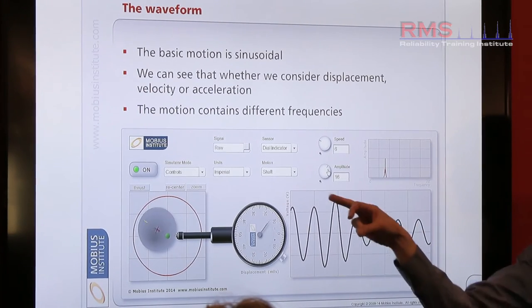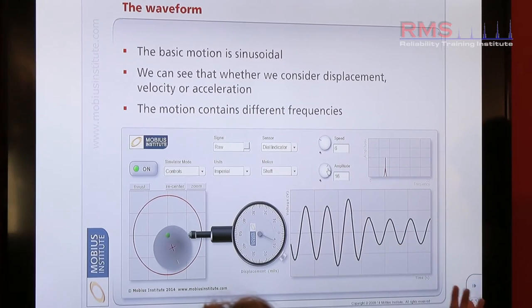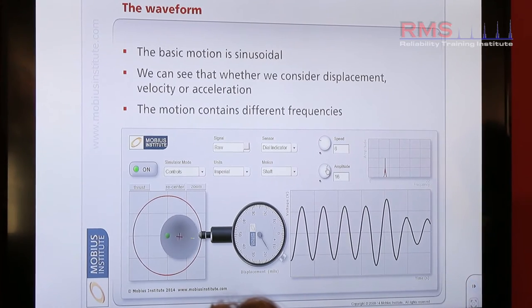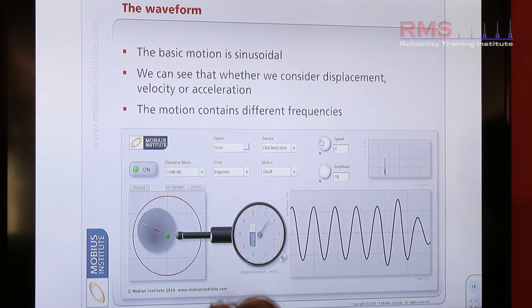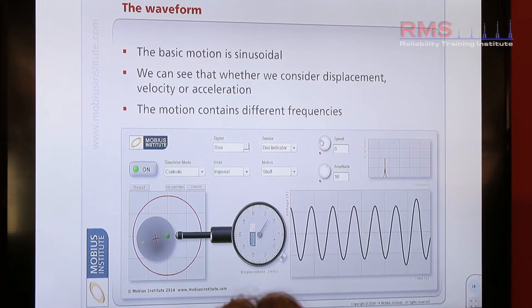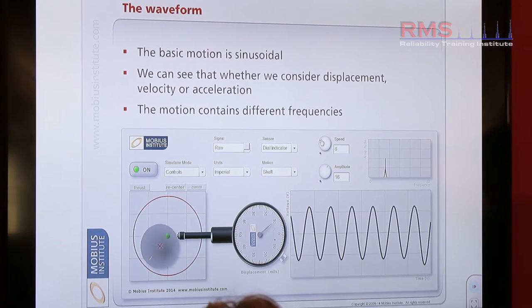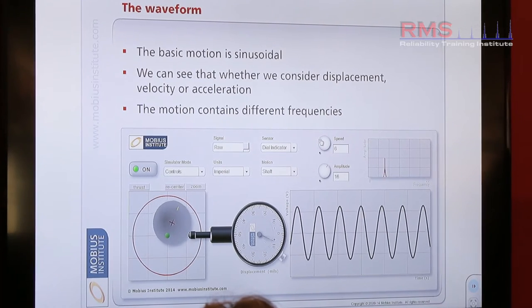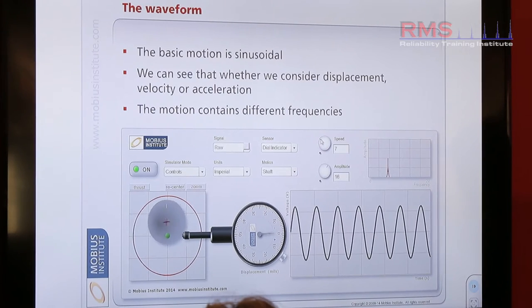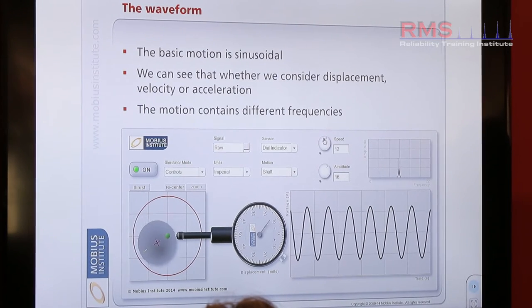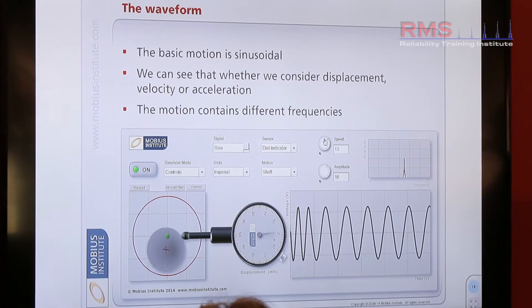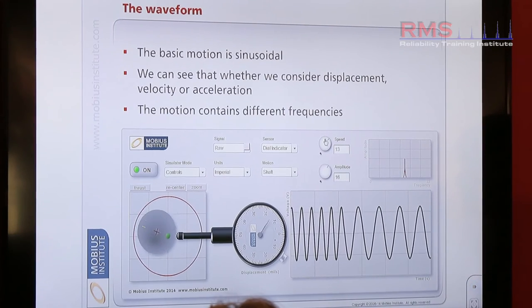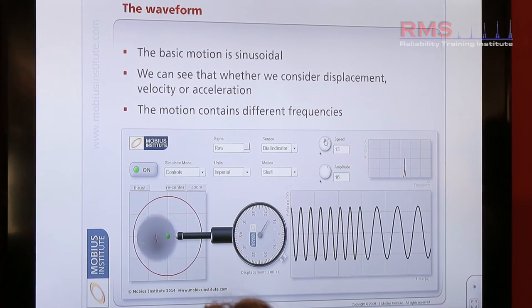We can see that the amplitude of the signal has grown due to a heavier mass on the fan maybe that's mounted on that particular shaft. If the speed changes, the waves get closer together. The speed increases but it takes less time to do one full rotation. So one thing that's very important about vibration is that we measure and correlate speed with the signals. Speed is an incredibly important measure that we need to understand.